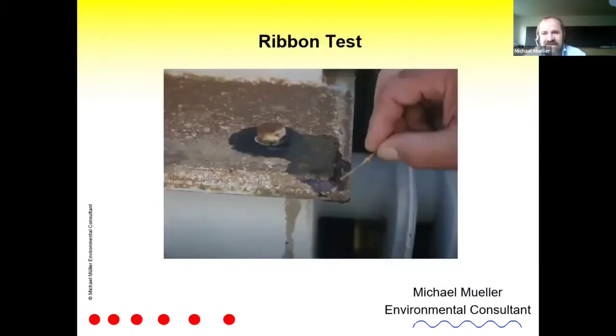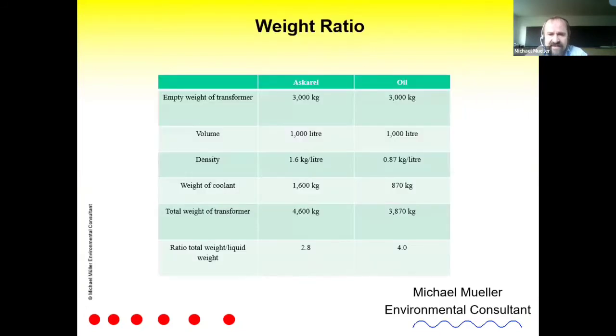Next slide. That's a ribbon test. If you have a leakage like that, try to find some stick or paper and put it in. It looks like oil or water, but it is Askarel. From an Askarel that comes out, the trichlorobenzene will disappear and will harm the ozone layer. The same with low chlorinated PCBs, they go up to the ozone layer as well. But what remains is more sticky, like honey or chewing gum. You put some ribbon in and you see the ribbon will stay for some time. That is a good hint that it is Askarel. Next slide.